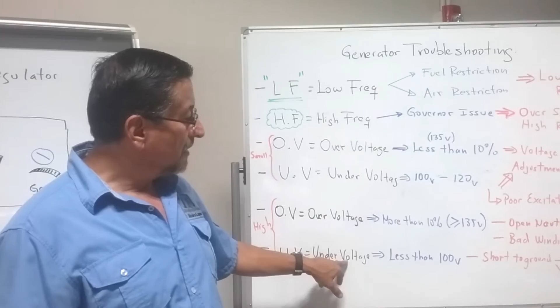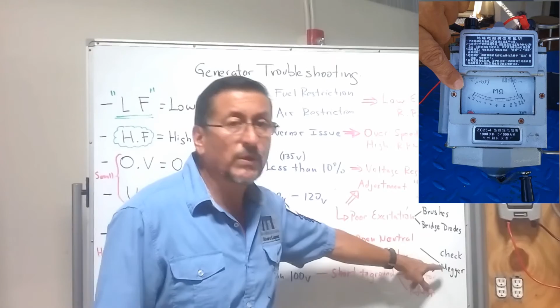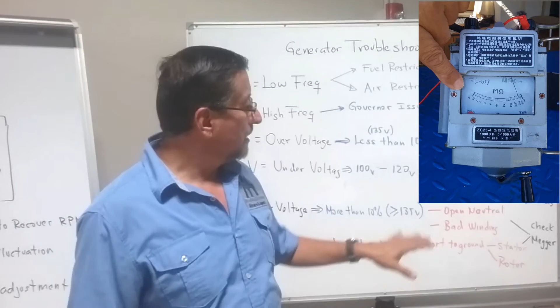Another possibility is UV, undervoltage, but more than 10%. For example, the output voltage is 80 volts or 70 volts. In that case, probably you have a short to ground on the stator or on the rotor. Both of them can be checked with the megger. I explained in the other episode the procedure to check with the megger if the winding on the rotor or on the stator is in bad condition. This is overvoltage and undervoltage.